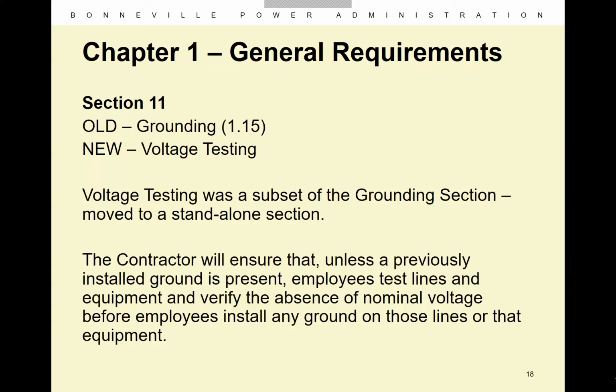Voltage testing was a standalone section, and the information was moved up in the new C-sharps document. We changed the location to make it flow better, and provided additional language to ensure contractors identify and test for voltage prior to work. We referenced language from our BPA work standard to give more guidance on voltage testing. We clarified procedures to allow for identification of any circuit being tested, clarified the minimum crew size, and provided additional clarity on installing and removing personal protective grounds.